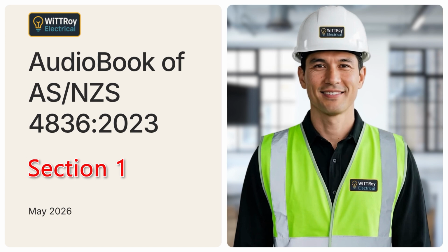Clause 1.4.23. Incident energy. Incident energy is the amount of thermal energy reaching a surface at a certain distance from an electrical arc event. It is usually measured in calories per square centimetre. This value helps determine the possible burn risk and what level of PPE may be needed.